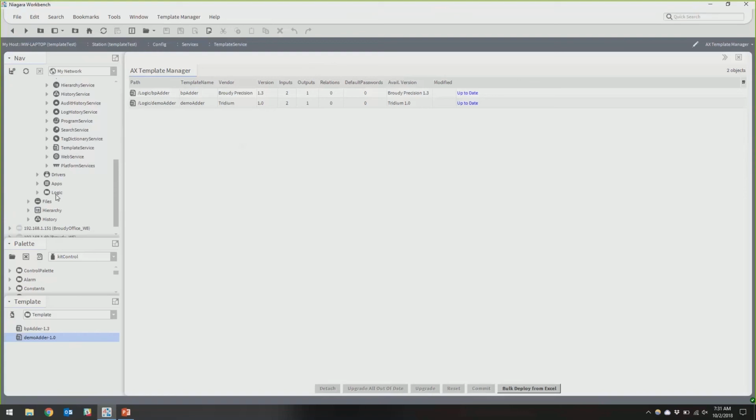Is it an electrical problem? Is it a location problem? Yes, all the above. Let's fix it with software. It's like 300 feet away, so it's a good distance. The JACE is on the 16th floor, the DP transducer's on the 4th floor, and kind of over a ways, maybe 100 feet over, 200 feet over.